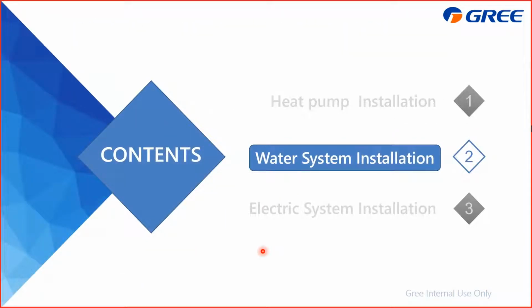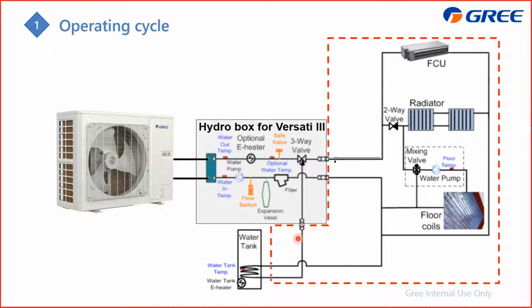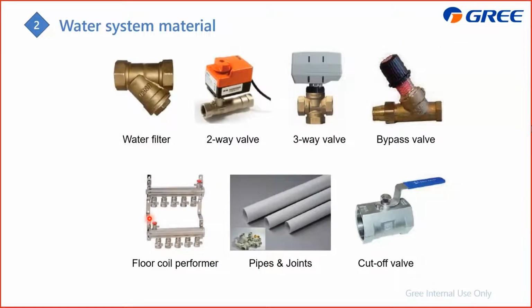And the next part is the water system installation. For this part, all the water system also belongs here. This is the material you may use during the water system installation, including the water filter, two-way valve and three-way valve, especially for the monoblock series. Later I will install the Y-strainer, and also the bypass valve, especially for the FCU. And if you need to install the flow switch, this is the flow switch, also called the water flow switch, and also including the pipes and joints, and also the cut-off valve.